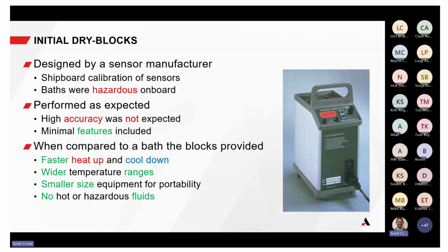And when compared to a bath, it was faster heat up and cool down, wider temperature ranges. It was smaller size equipment to move around and much more portable, and no hot or hazardous fluids. So, you know, it minimized the burn hazard. It also minimized the spill hazard. Silicone can be very slippery, and taking that liquid out of play made it a lot safer for the technicians.